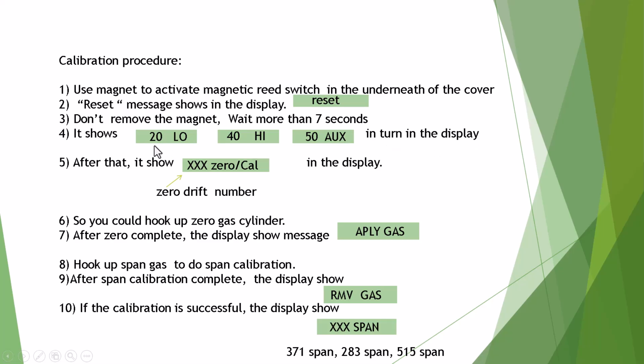20 LO means 20% low alarm. 40 HI is 40% high alarm. 50 auxiliary is not the high alarm, it's the auxiliary alarm; it's the exceed setting. Okay. After that, after it shows 20, 40, 50, it then shows zero cal. Near the zero, before the zero, it displays a number. This number is the zero drift number. Okay, so when you see this zero cal, you can hook up the zero gas cylinder.